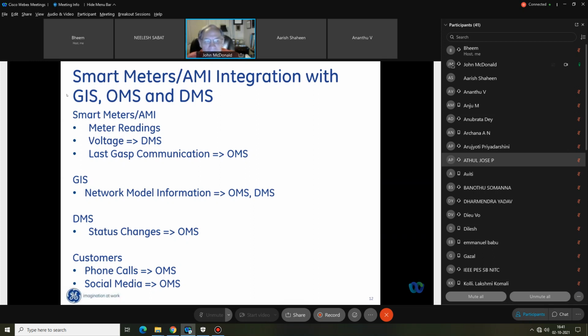The geographic information system is the reference system for the network model for outage management and distribution management. We take status changes in the distribution management system and send those to outage management. For instance, if a feeder breaker trips, we know that all the customers on that feeder now have an outage. That one status change can tell the outage management system all the customers that now have an outage.